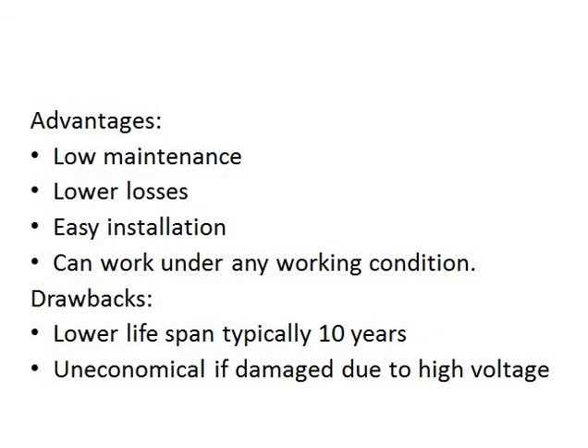The drawbacks of the capacitor banks are the lower lifespan, typically 10 years. Further, they are uneconomical if damaged due to high voltage. Although the cost is an important parameter, they are subjected to high inrush currents. Capacitor switching does happen, and it may lead to complete failure or failure of the protective devices associated with the capacitor banks. So one should always consider these aspects while installing a capacitor bank.